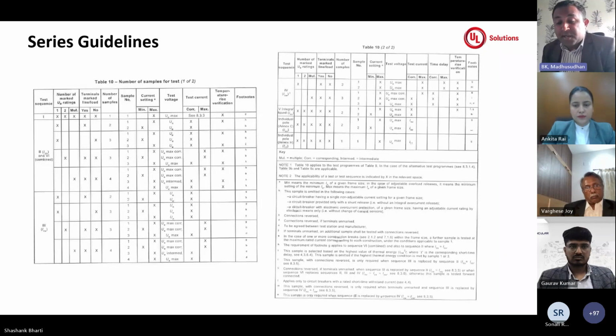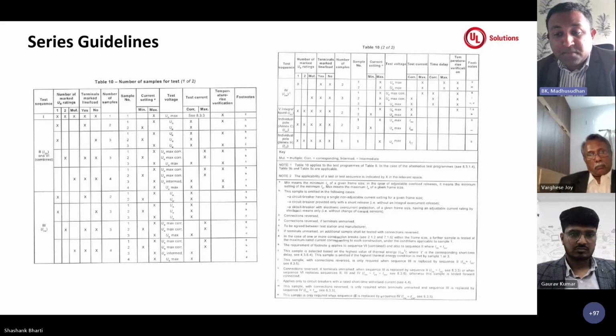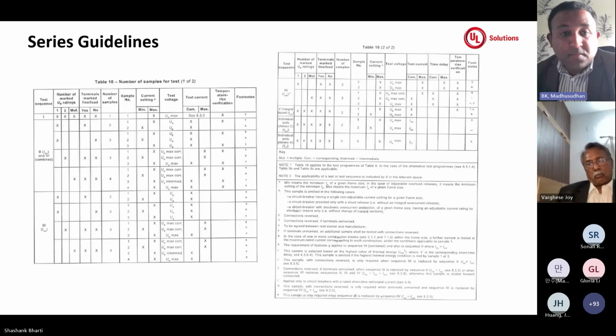Yeah, and the standard also gives references from table 10 where, based on the declaration, for example, if a range has multiple voltages within the particular range, and also the breakers are being marked with terminals and without terminals, and also, as said, based on the number of poles and also the current settings on the breaker. So normally some of the breakers will have flexible settings where we can select the current ratings from minimum range to maximum range. So based on all this declaration, table 10 gives us a reference for what number of samples to be picked for each sequence.